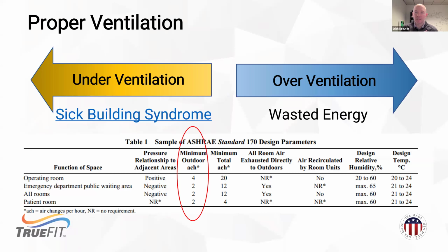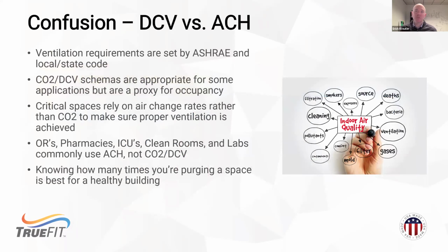And again, lifting a little bit out of the ASHRAE standard here is 170. Depending on the type of space you are, if they're critical environments, ASHRAE is going to recommend certain air changes per hour to make sure that space is properly conditioned and free of contamination. I will mention air changes per hour as the metric here. And as we talk to people, especially as new standards come out, Title 24 in California has some ventilation standards for schools and things like that.